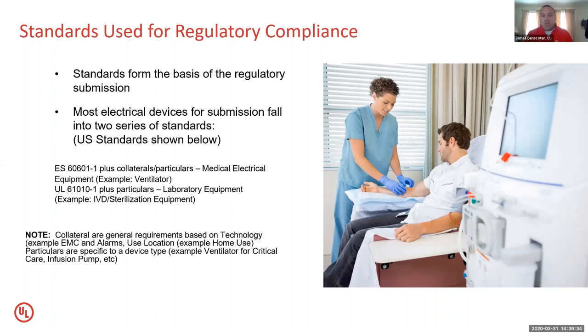Additionally, we'll have devices that will be more for the analysis. And this comes down to where you start talking about some of the test kits. And you'll see a lot of these devices when they actually talk about the device that processes and uses these tests to determine if someone has COVID-19 or any other one, such as flu type A or type B, will fall under the requirements of UL61010 plus the relevant particulars.